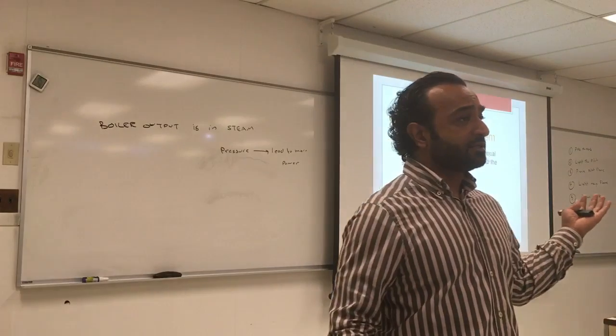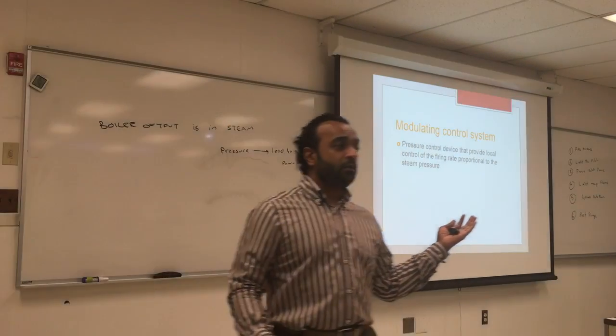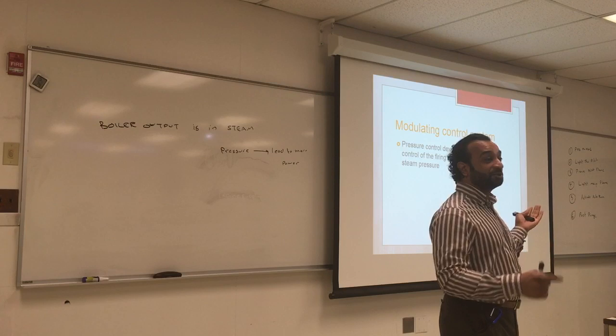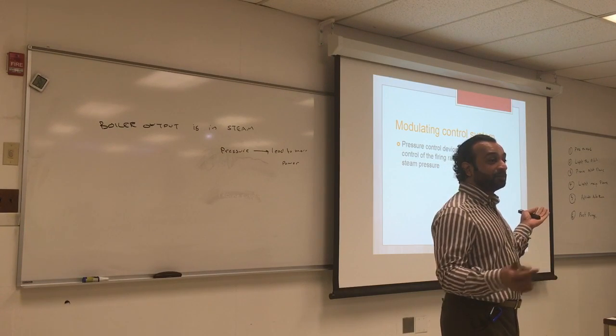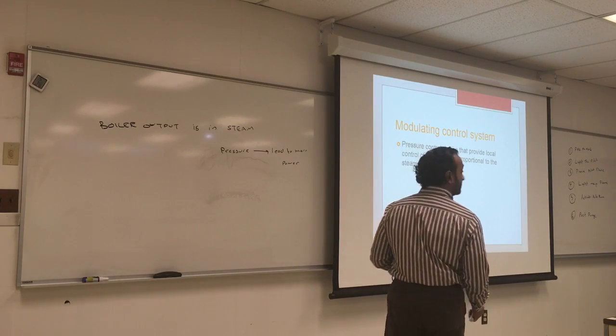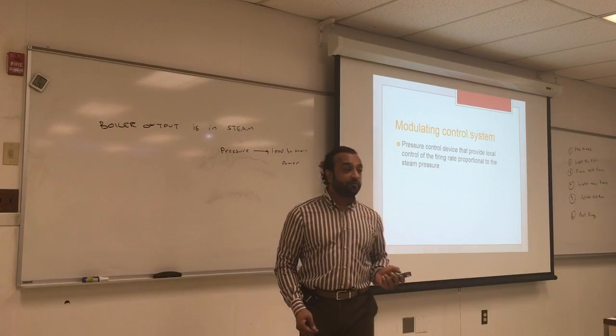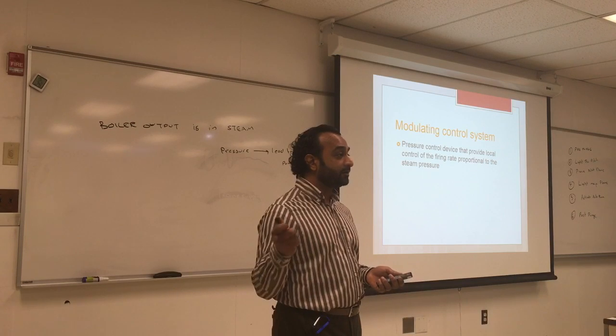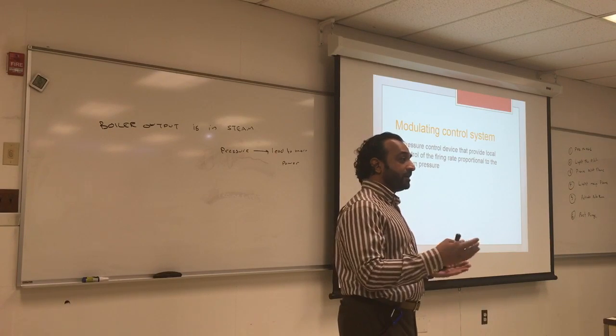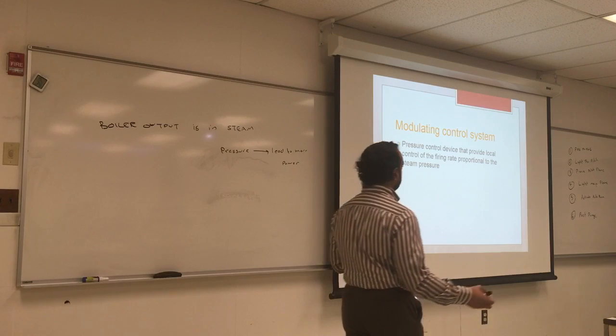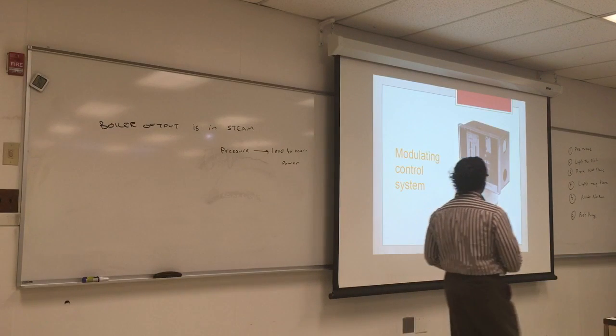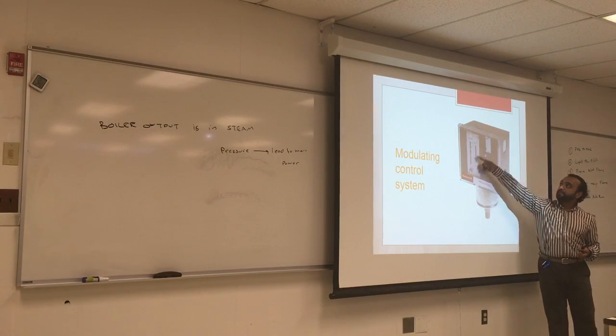The steam is the output and the input is fire. What do we control when we try to make fire inside the chamber? To control the firing rate, you control the fuel — think of the car again. The more gas you put, the more engine power you get. So we modulate the fuel. The fuel has its own regulating damper, so the more fuel, there's going to be some kind of relationship where you input more air to burn the fuel.